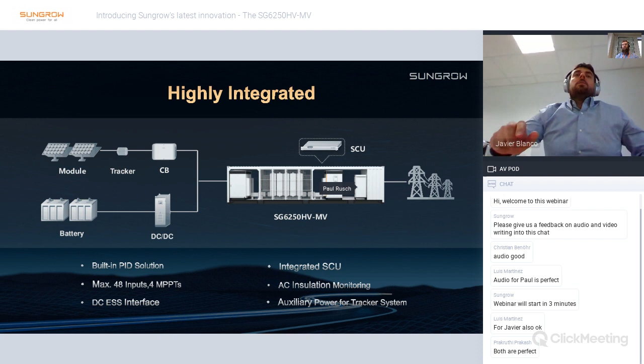We are talking about a highly integrated solution. As we can see in the picture, this could be the layout of the complete PV plant. Considering the PV side, the modules, the combiner boxes, trackers, etc., connected to the inverter, on the other hand, we can couple on the DC side an ESS system composed of battery plus DC-DC converters here. But in the end, once everything is connected to the MV station, the connection is directly to the MV grid, and that's it. There's nothing else to be done on the installation.